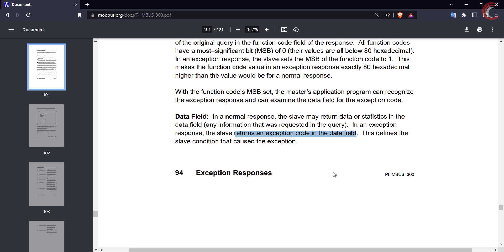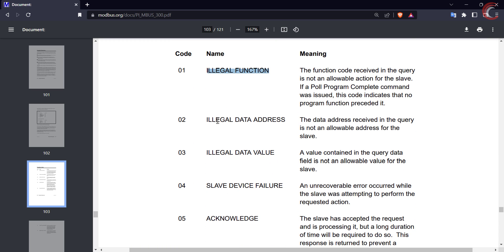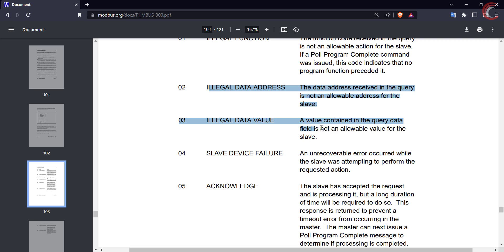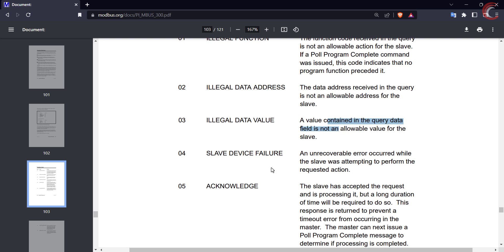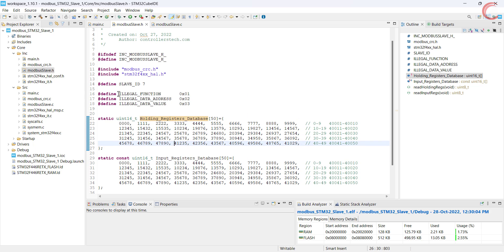In the data field, the slave returns the exception code. The exception codes can also be found in this document. We will work with the first three of these: illegal function — when an unknown function code is received by the slave; illegal data address — when the data address requested by the master is not available in the slave; and illegal data value — when a value in the query data field is not an allowable value for the slave. We will use these exceptions and see them in working.